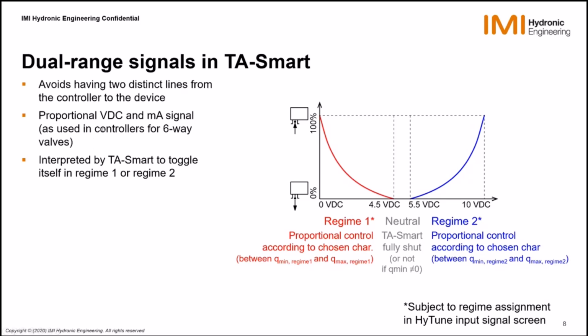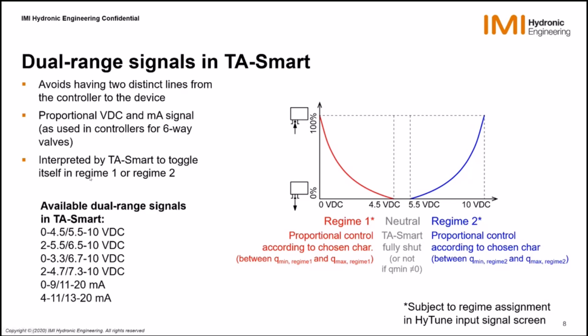We have proportional voltage or milliampere signal as used by controllers for 6-way valves, so nothing really new. I mean, TA-Smart can be connected to just the same controllers as you would control basically a 6-way valve or a setup like we have with the slider CO. And simply TA-Smart will interpret the voltage or the milliampere value to toggle itself between regime 1 or regime 2. The available dual range signals for TA-Smart are by default this one, the 0, 4.5, 5.5, 10.